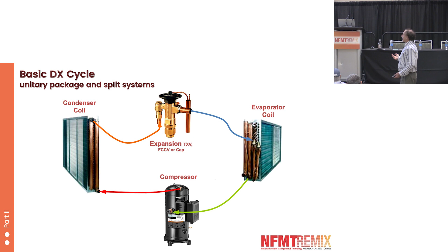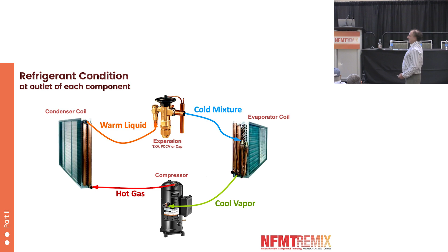So just taking the next step in there, this is what the condition of the refrigerant usually is, or I think almost has to be, yes. So we've got from the evaporator coil a cool vapor, exiting the compressor is a hot gas, then exiting the condenser coil is a warm liquid, and then you get your cold mixture. So if this is as far as you went, and you put your hand on the tubing, you would say, okay, this unit's working, and you could be done right there.